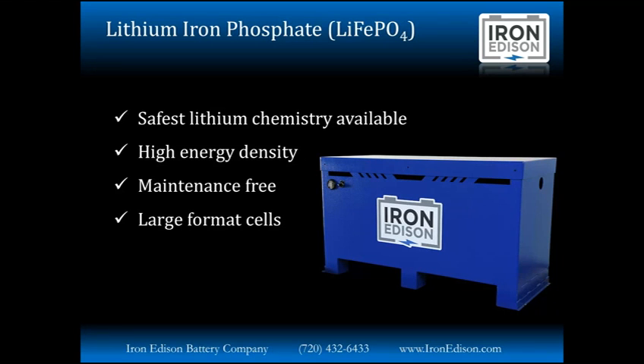It has the highest energy density of all the lithium batteries, which makes it the least stable. In the event of a catastrophic failure with a lithium cobalt, you're going to have a self-sustaining fire where it literally is producing its own oxygen, so it's very difficult to extinguish. Really, the only way you can extinguish a lithium cobalt fire is with a special Class D fire extinguisher. They're kind of rare and very expensive. Most times you just have no choice but to sit back and watch it burn. And that safety reason is specifically why Iron Edison chose the lithium iron phosphate chemistry for our lithium batteries. Catastrophic failure with lithium iron phosphate, you're going to have venting steam, and that's pretty much it.